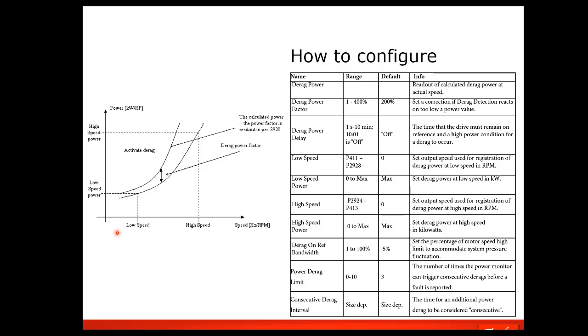And then you set what these speeds are in here: low speed, high speed, and then what is the power level, the low power point and the high power point. And then there's a bandwidth, what's the bandwidth between running and that. You can set that other than the correction factor.